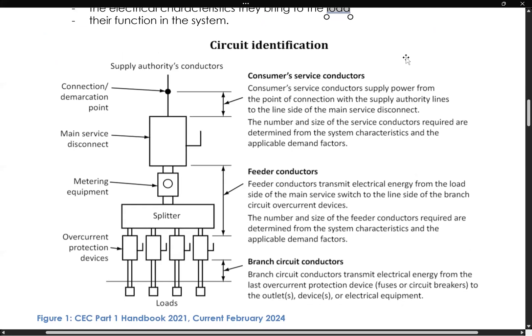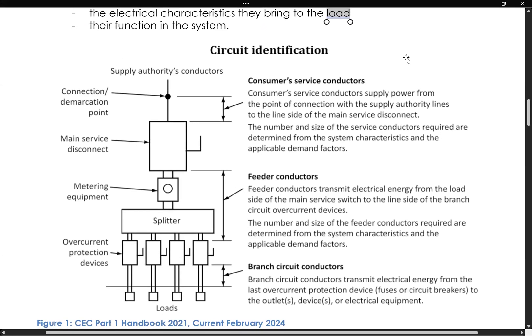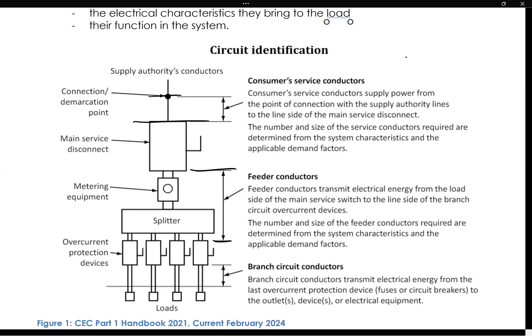And here's just an example of a typical circuit and what we would call our feeder conductors to be in this section here, that includes our metering equipment up to our overcurrent protection devices for our branch circuits, and the consumer service conductors to be from the demarcation point to that main service disconnect. And then feeder conductors in between, and then of course the branch circuit conductors are the ones that are going to take the energy from that last overcurrent protection device, our fuses or our circuit breakers, on to our outlets or our devices or our electrical equipment.